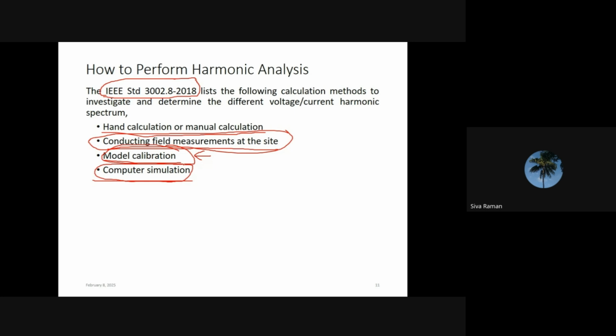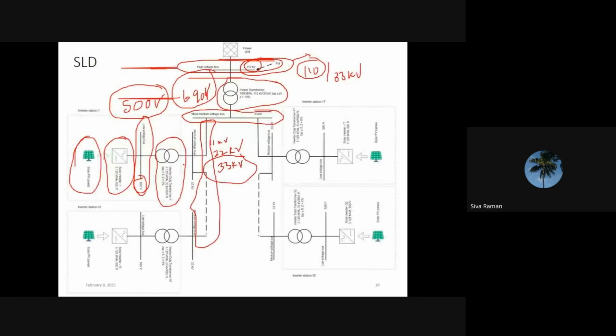These software have the feature of representing the harmonics in the system, and we can model each and every element present in the single line diagram, starting from the solar panel, solar inverter, inverter duty transformer, then collector network, then transformer, then transmission line. If there is any reactive power compensation device like capacitors, filters, STATCOM, reactors, we can model it, and we can do the simulation.